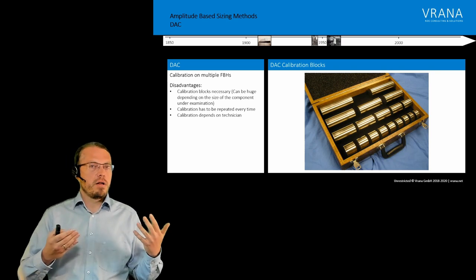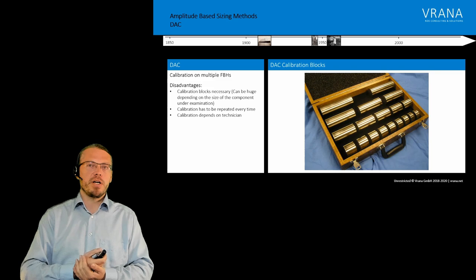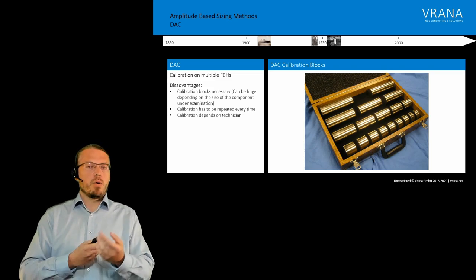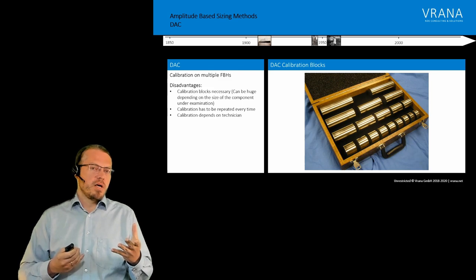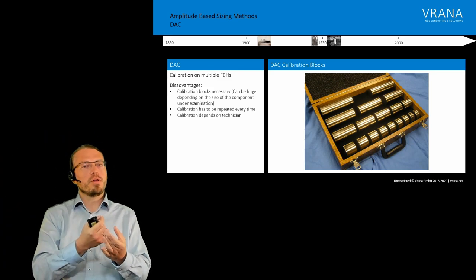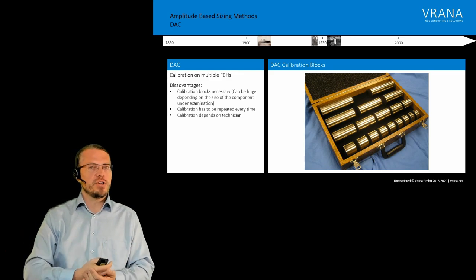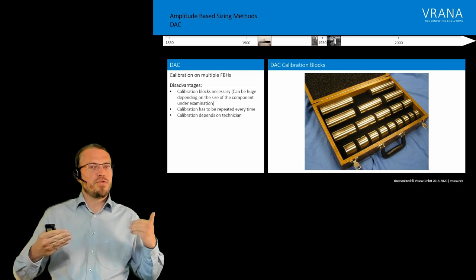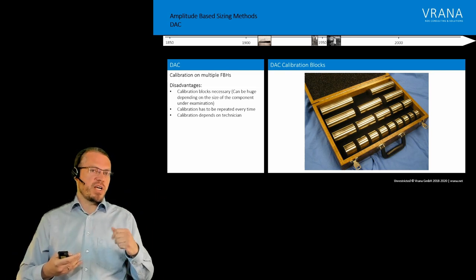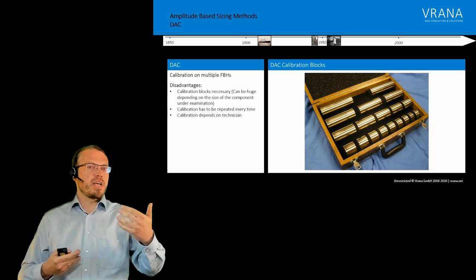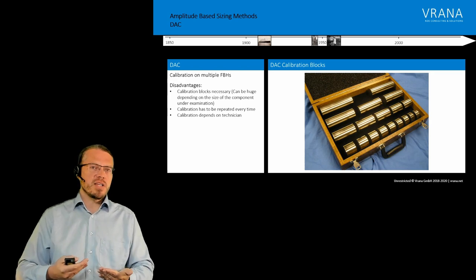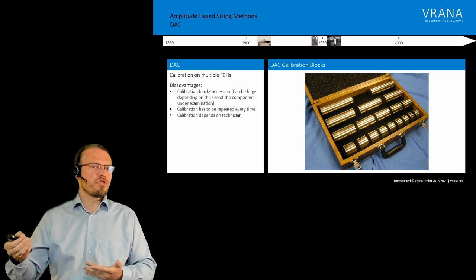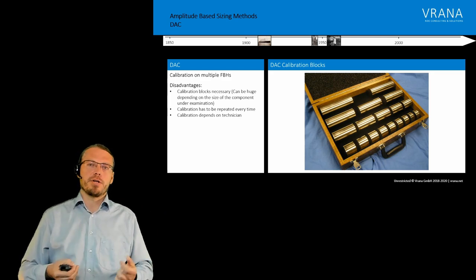Now one method to use this correlation is so-called distance amplitude calibration blocks, like you see them here in this set. And each one of those blocks has a flat bottom hole inside. So you put your probe on all those different lengths with all those different flat bottom hole diameters. And you get those curves. And once you find a real indication, then you compare the reflectivity to reflectivity of those calibration blocks. And then you can say okay, this indication actually reflects like a flat bottom hole with one millimeter diameter.